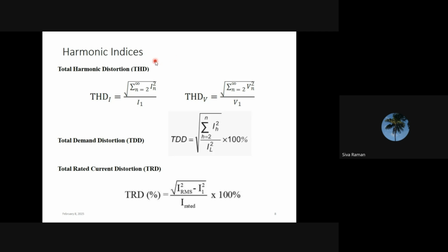The commonly accepted methods are total harmonic distortion. Total harmonic distortion is a summation of all the harmonic components divided by the fundamental component. We can calculate the total harmonic distortion for the voltage as well as the current. The IEEE standard 519 also has a limit for the voltage harmonic distortion, especially for the voltage. Similarly, IEC also has the maximum recommended limit for voltage total harmonic distortion.